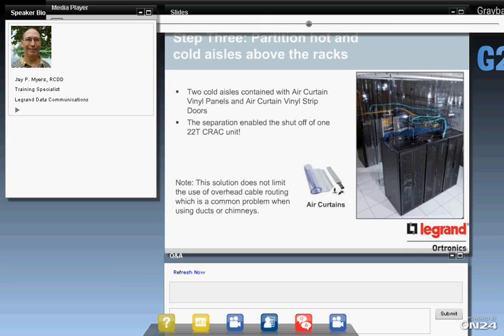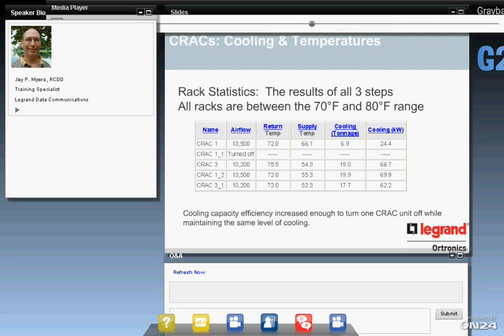Just by installing these, we're able to shut off 1 of the 5 CRAC units in the data center. This is also very easy to work with overhead obstructions. Most people now want to put their cabling overhead, and this is very easy to work around. So here's our chart now. We've turned off 1 CRAC unit. Depending on where you are geographically and how much you pay for your electricity, that could easily save you $25,000 a year in electricity. Notice also in the return temperature column, these temperatures have edged up a little bit.